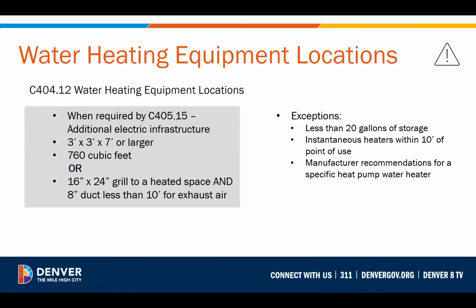So as we noted in those design considerations, they're a little bigger. So you need to have a certain size for that closet for the water heater, or you need to have a grill and ductwork to allow for pulling air or exhausting air. Some exceptions would be really tiny water heaters, smaller than 20 gallons of storage, instantaneous within 10 feet of the point of use for the hot water. Or you can also, if you're future proofing around a specific manufacturer's heat pump water heater, you can follow those recommendations if they're different than this requirement.